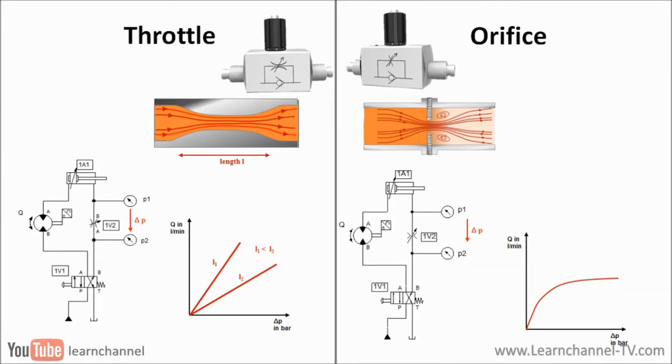The graph below shows a comparison of the volume flow between a throttle and an orifice as a function of the pressure difference. As you can see, the volume flow at an ideal throttle with a soft transition from thicker to thinner diameter increases roughly proportional to the pressure, provided that the flow is maintained as laminar.